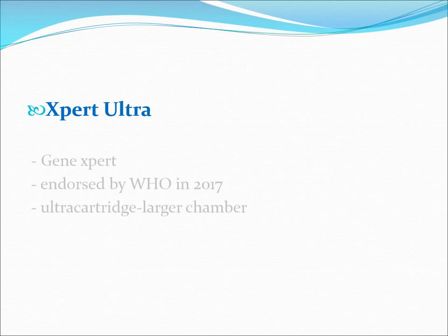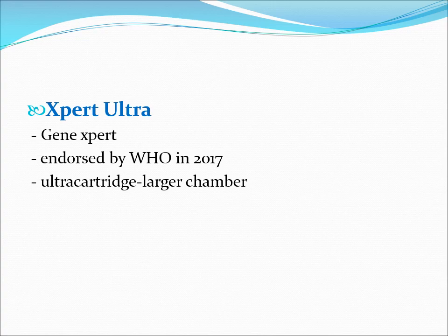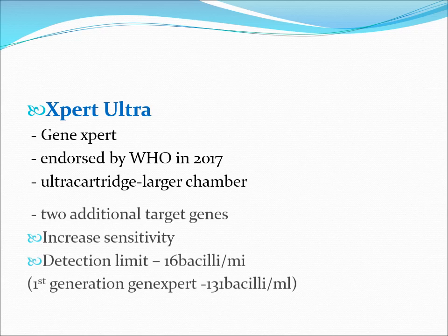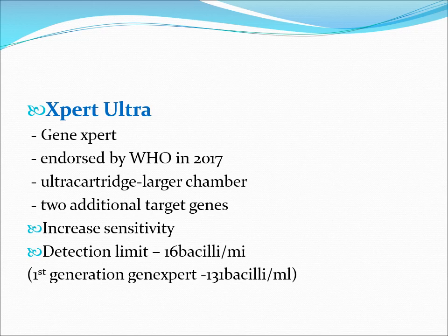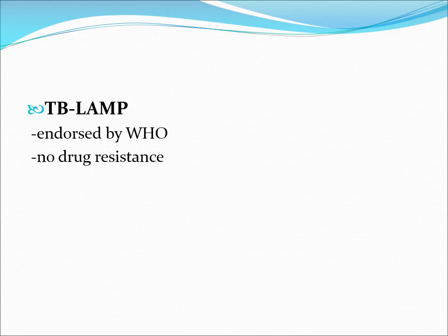Xpert Ultra is a modification of GeneXpert, also endorsed by WHO for TB diagnosis. It has a larger cartridge chamber and two additional target genes, giving increased sensitivity. The original GeneXpert detects as low as 131 bacilli per mL, whereas Xpert Ultra can detect as few as 16 bacilli per mL. TB-LAMP is also WHO-endorsed, but does not provide information on drug resistance.